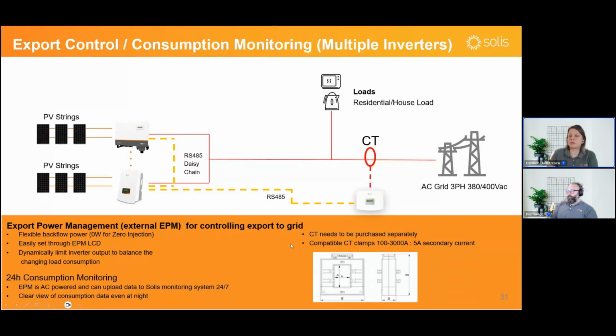This solution, other than just export management, can also offer 24-hour consumption monitoring, because this EPM is powered from the AC side, so it doesn't matter whether you have any PV generation. If you have, for example, loads that also work throughout the night, you're going to be able to measure the consumption of these loads during nighttime. And this information can be made available on the Solis Cloud app, on our monitoring platform, so customers can see their load consumption 24/7, which can be very important for some.